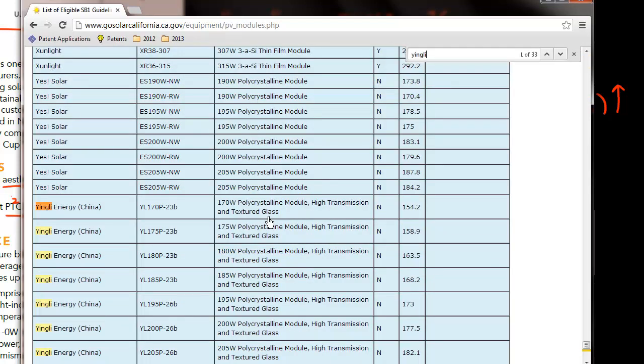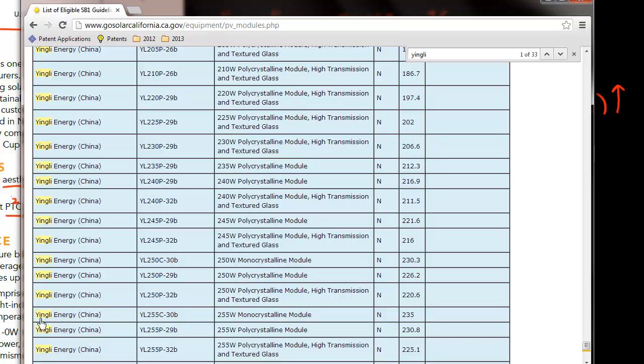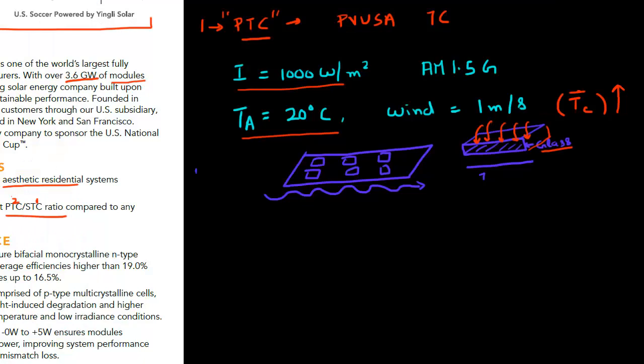So let me search for Yingli over here. So Yingli and then the panel number which I was using was this 30B panel over here. So I see that it says it's made in China. It says the panel number, then it says it's a monocrystalline silicon module. And then it has a PTC rating of 235 watt. So for this panel, the PTC rating as specified by the California Energy Commission is 235 watt.